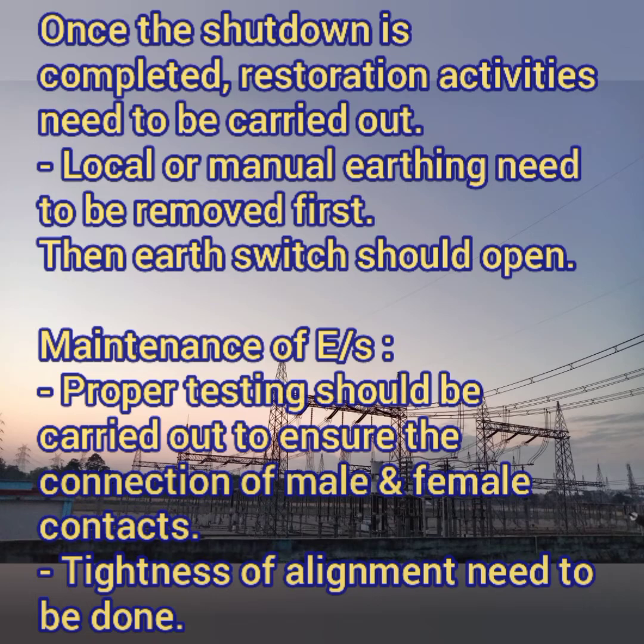Then the earth switch should be opened. For maintenance of your earth switch, we need to carry out some testings — first to ensure that the male and female contacts are making properly. So contact resistance measurement needs to be carried out for your earth switches. Then tightness and alignment need to be done, because due to the operation of the earth switch, the rotating shaft may get damaged or looseness can happen. In order to overcome this problem, we also do tightness checks for the earth switches. These are the basics and overview of the earth switch in a substation.